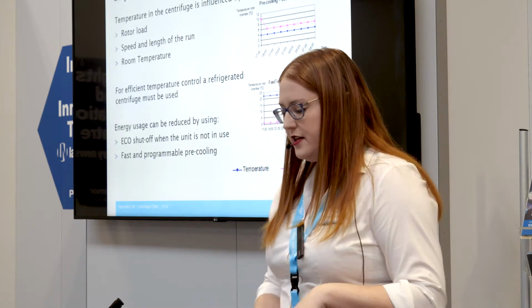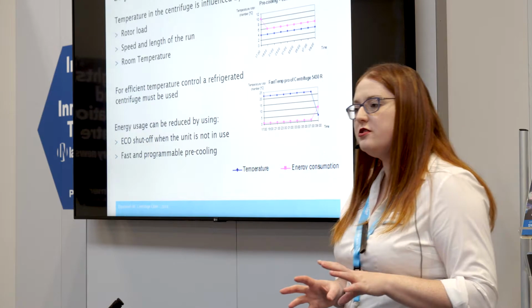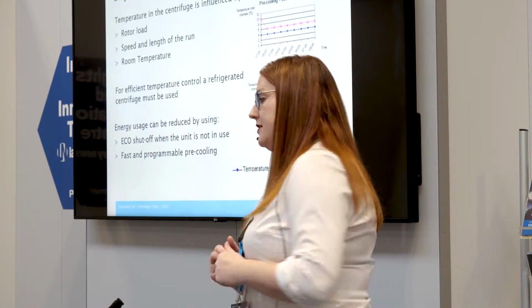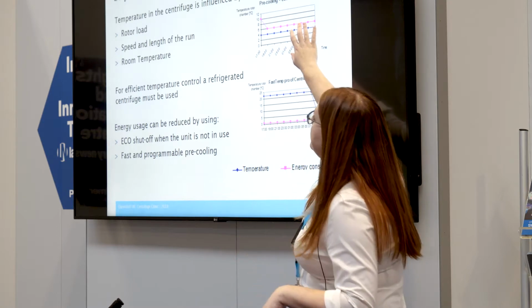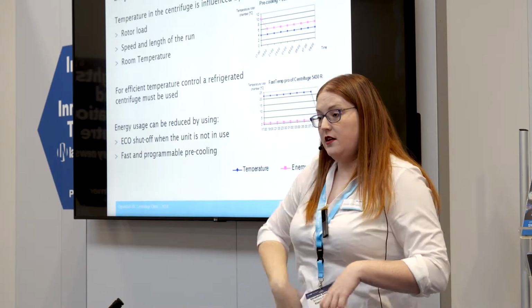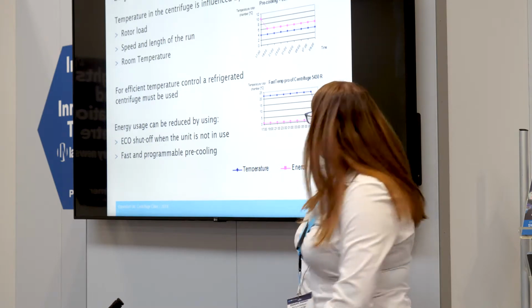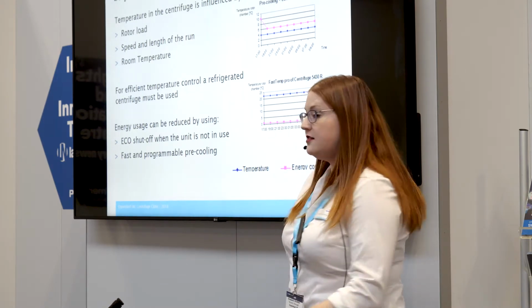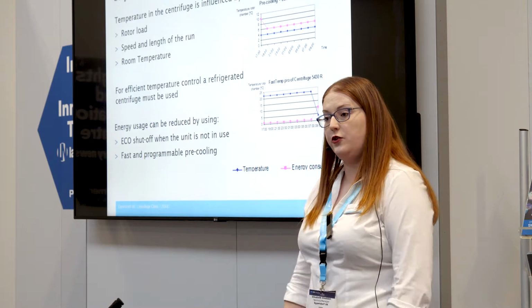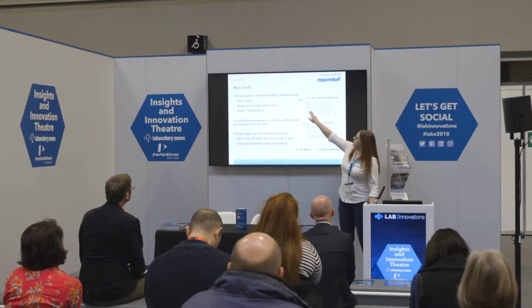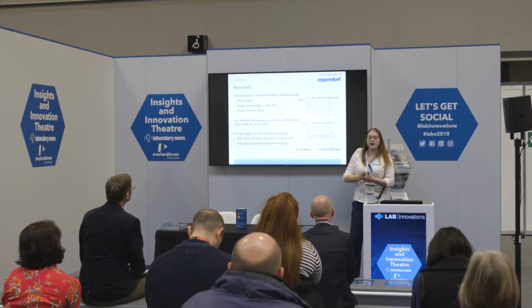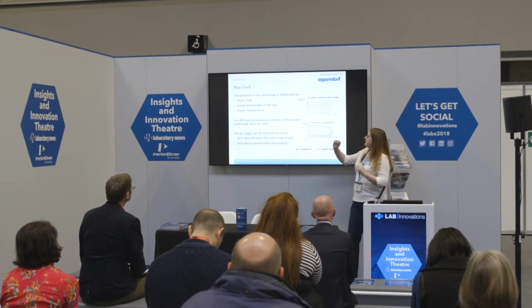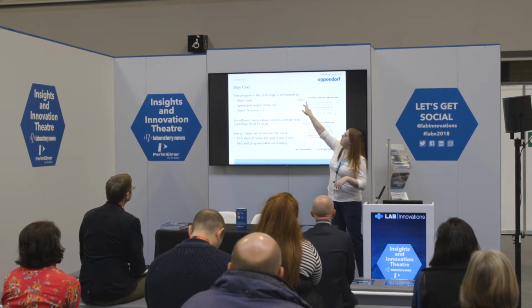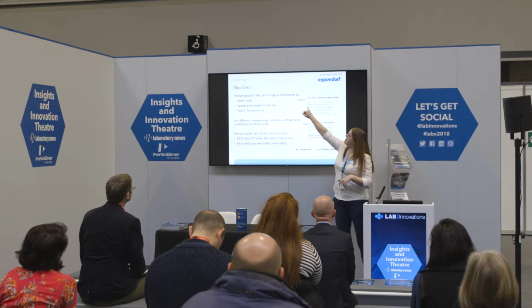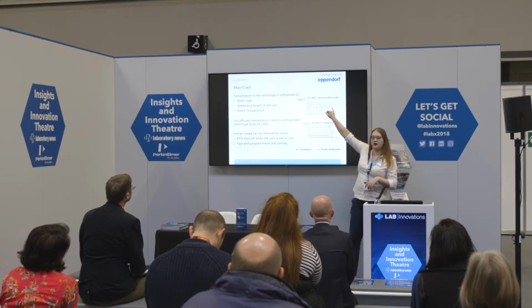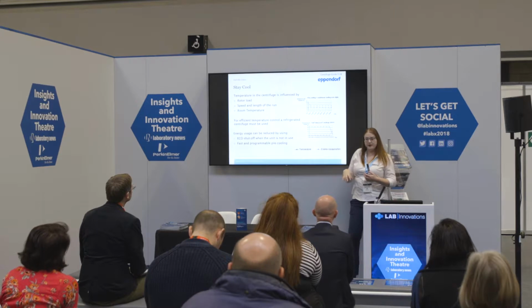And there are 2 different ways that most centrifuges use. They use one or the other in order to be refrigerated. So, in this graph, they use pre-cooling and then continuous cooling. So what happens is they cool it down at first to the right temperature, which in this case is 4 degrees. So they cool it down, and then they keep it at 4 degrees all night. So you can see the temperature is nice and consistent at 4 degrees all night, ready for them to use at 9 o'clock in the morning. That's great. But then if you look at the energy consumption, you use a ton of energy at the beginning to cool it down, but then you're still using quite a lot of energy this whole time keeping it cold. Okay?